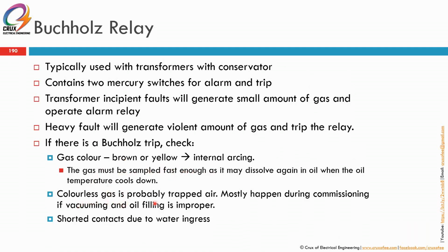Second, colorless gas is probably trapped air. This mostly happens during commissioning if vacuuming and oil filling is improper. If this is the first time you are filling up your transformer and you did not vacuum it properly, or maybe you are doing oil filtration, sometimes air gets mixed in, so there might be some trapped air within the transformer tank. This is considered not dangerous, but it will trigger nuisance tripping of the Buchholz. So what you normally do for new transformers is you have to really vacuum it until maybe 2 to 8 millibar.